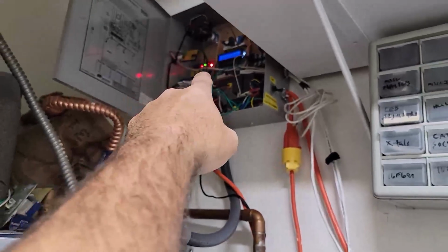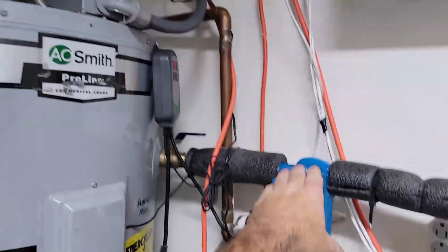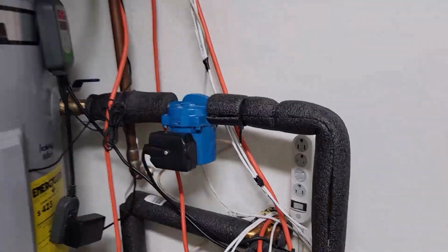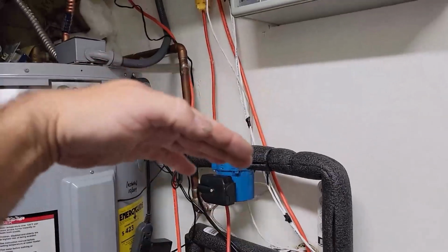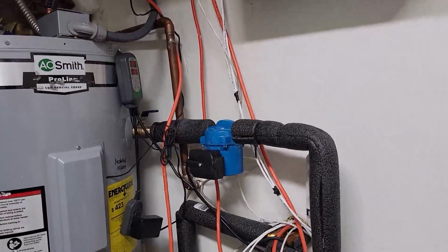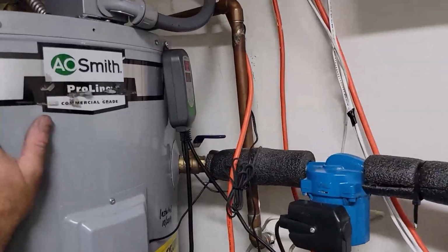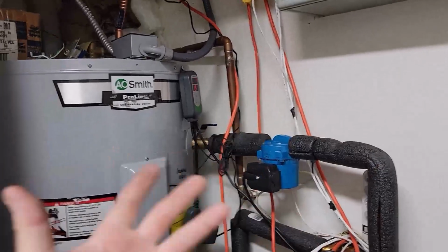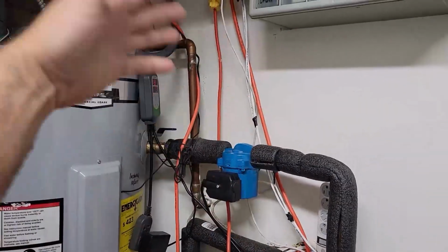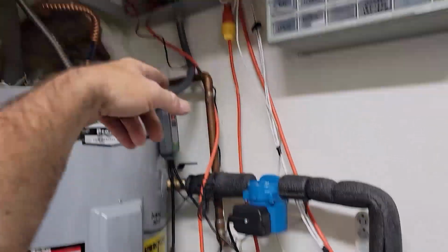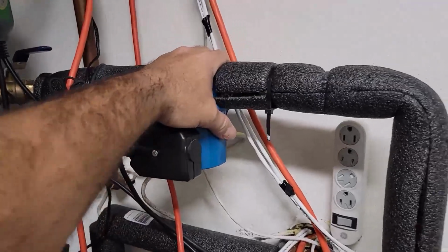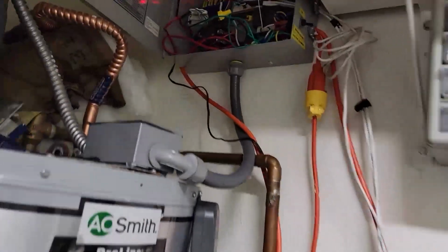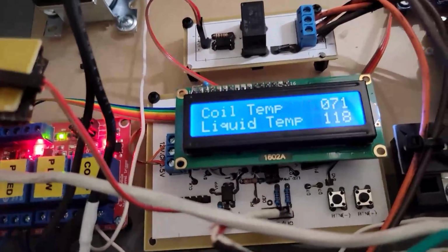So when the first relay comes on, it just goes to that to run this really slow. And then once the liquid line temperature gets above a certain point, to keep the head pressure right and give the tank a good heat rise, it's basically adjusted for heat rise. Once it hits like 110 on the liquid line, then it goes to high speed and just cranks this thing up full blast. And this time of year, it just kind of stays there. It says pump high speed.